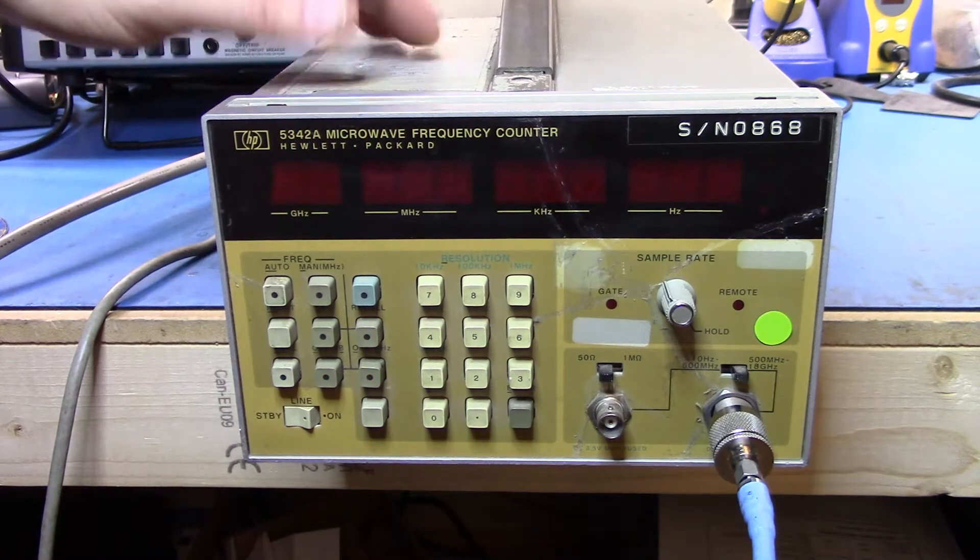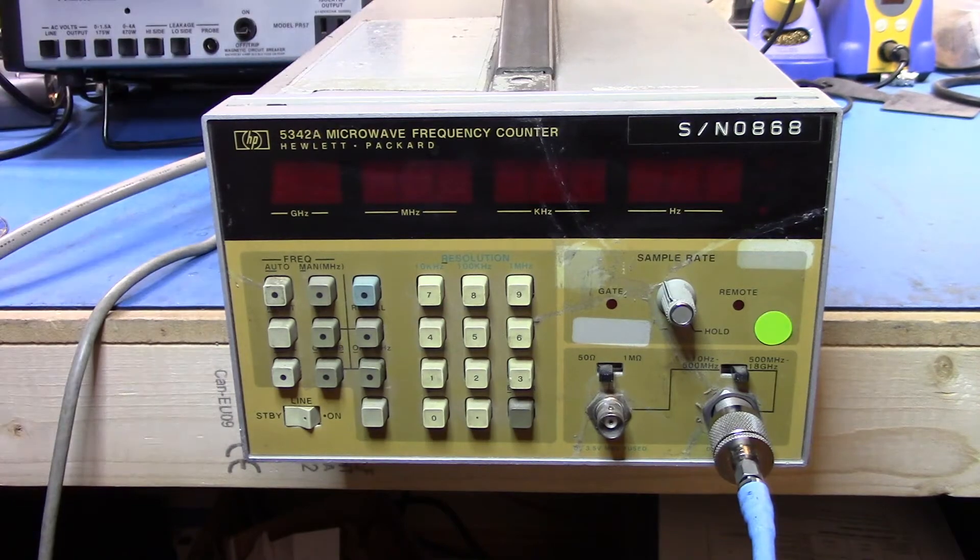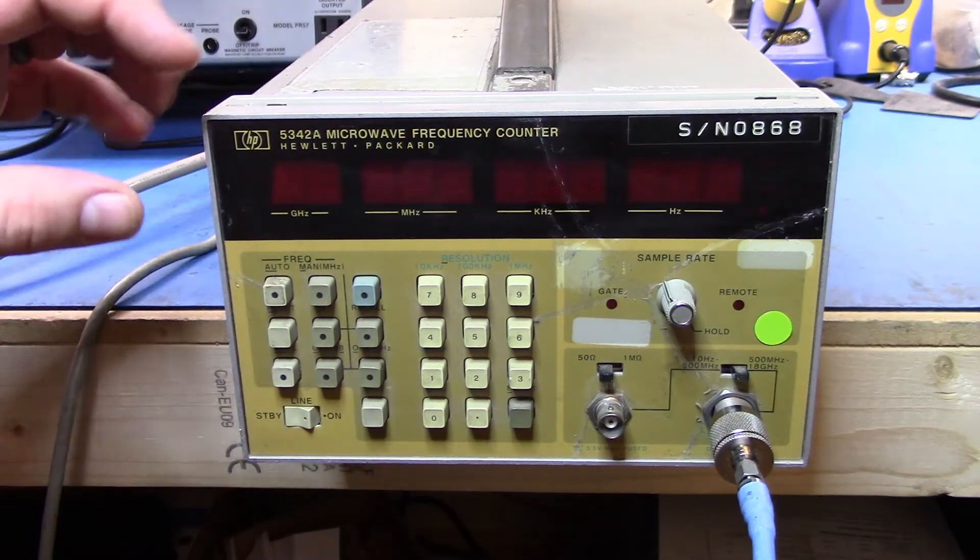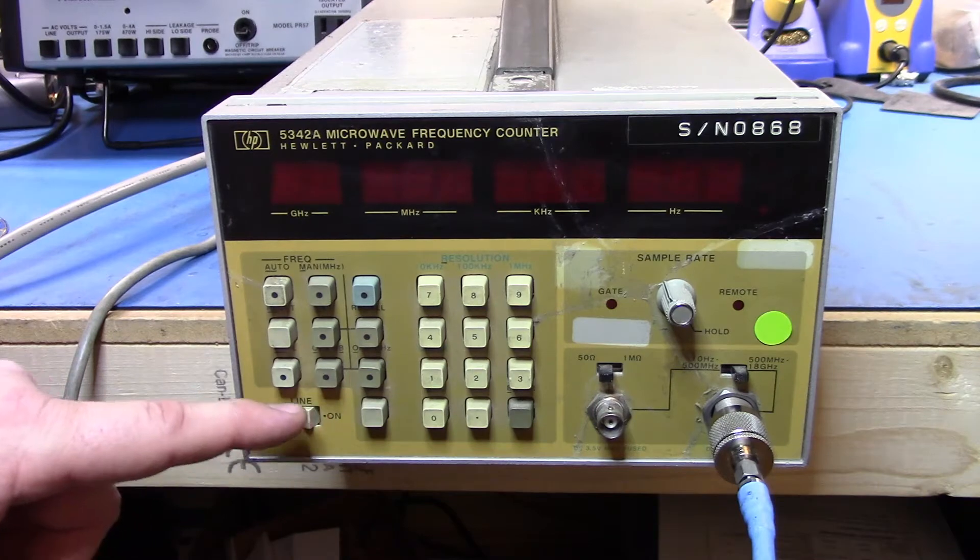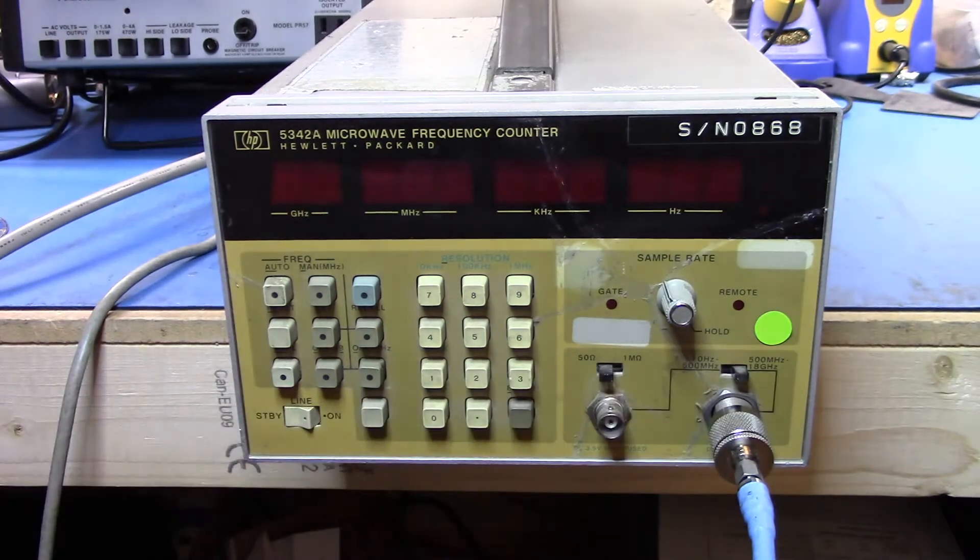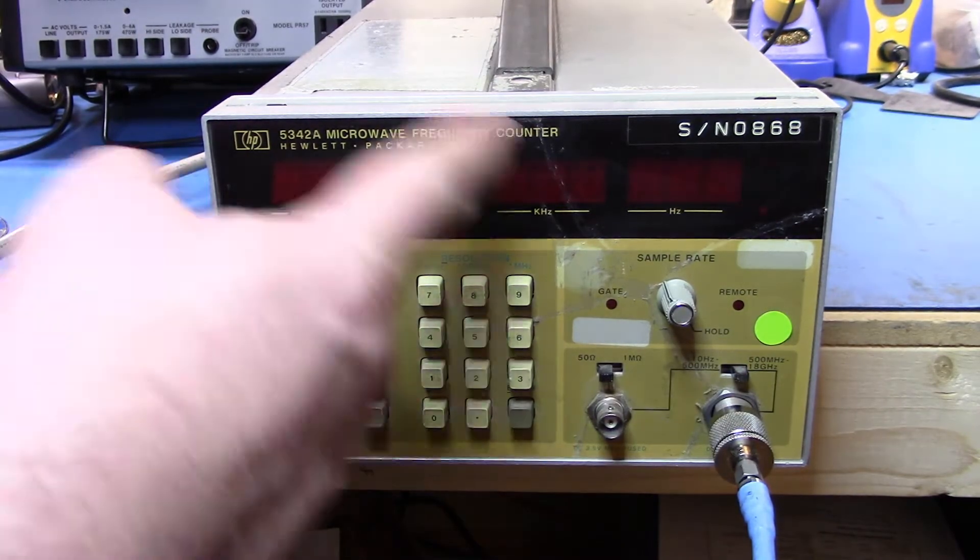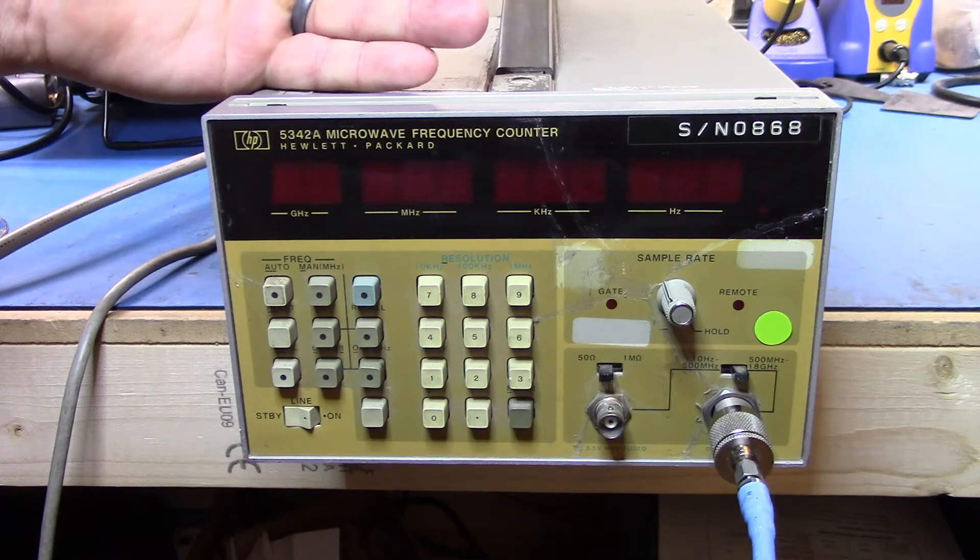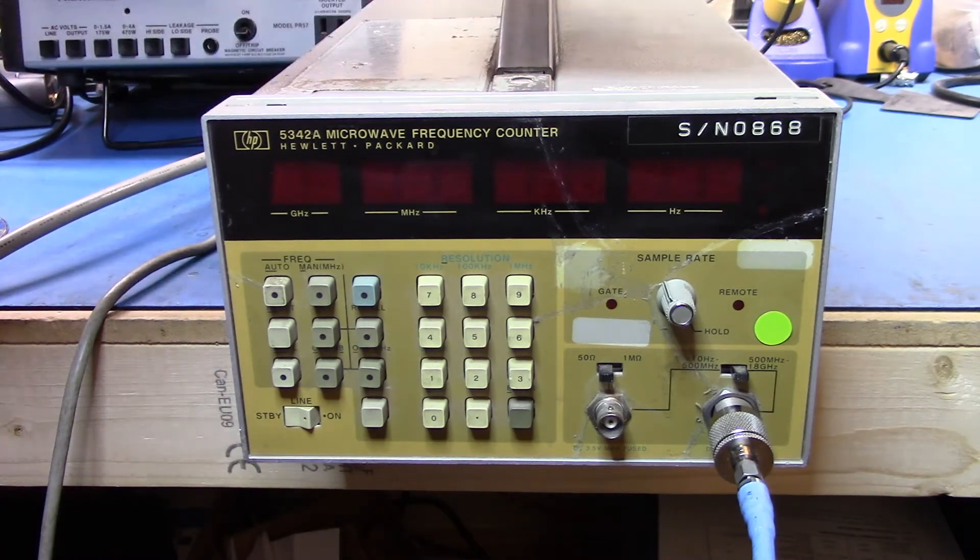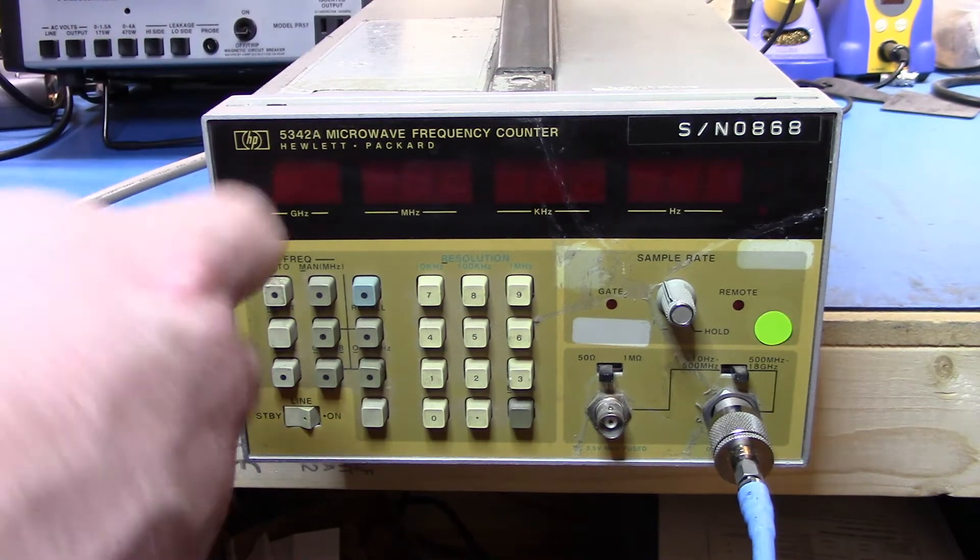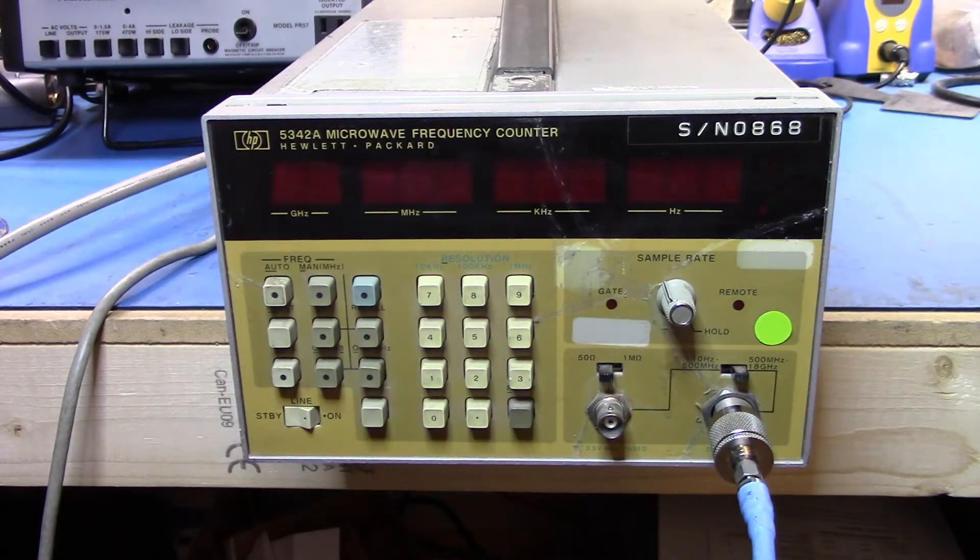Actually, it's interesting if you look at, if you go to the Keysight website and get the manual and look at the block diagram, everything that comes out of this is actually done on a counter. And this particular one has the amplitude capability on it, which is, I think, option 001. And basically what that means is that it can check the incoming signal and also give me what the amplitude as well as the frequency is. And it does that by taking the amplitude, creating a frequency based off the voltage of the amplitude, and then that sends that frequency off to the counter. And so the counter can then provide the microprocessor with information about what the amplitude is, which I thought was an interesting way of doing it. So everything is counter based in this unit.